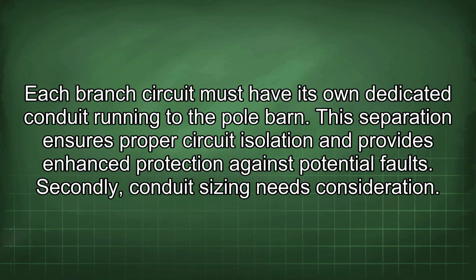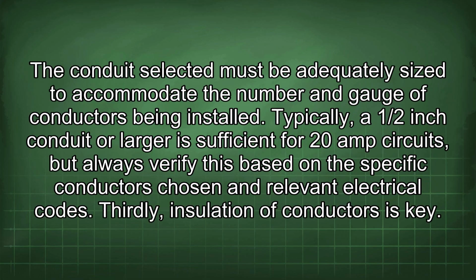Secondly, conduit sizing needs consideration. The conduit selected must be adequately sized to accommodate the number and gauge of conductors being installed. Typically, a 1/2-inch conduit or larger is sufficient for 20-amp circuits, but always verify this based on the specific conductors chosen and relevant electrical codes.